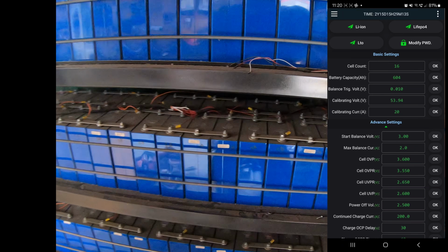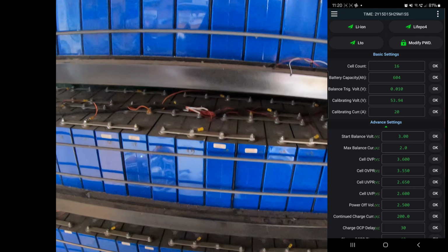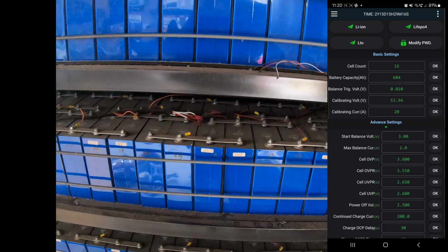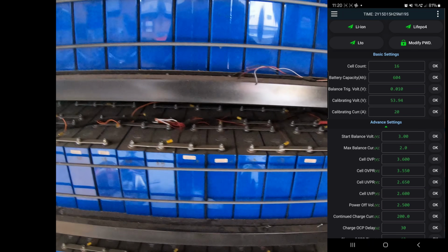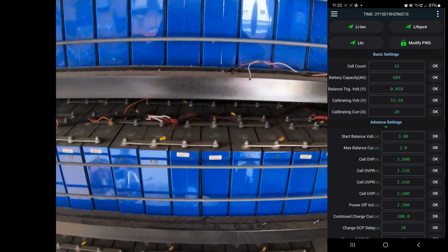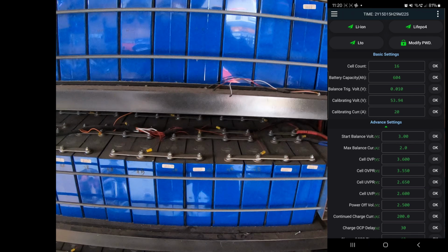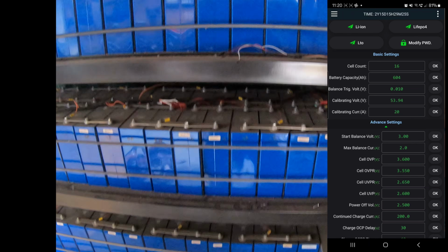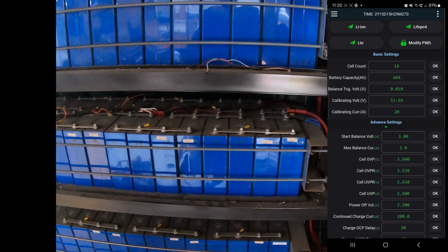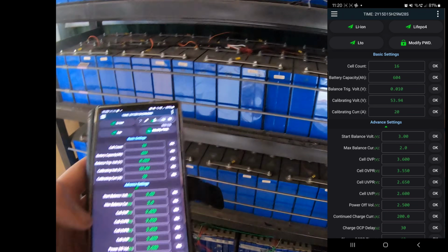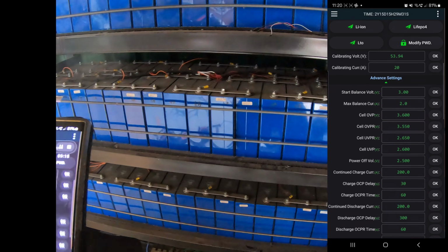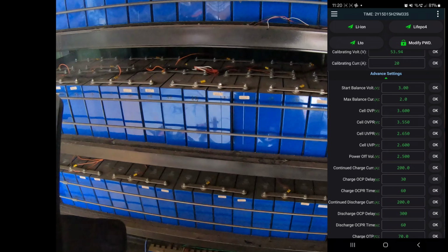What we do is periodically ramp the voltage up to 57 volts so that we can give the balancer the best chance possible. We do that for about a month, and then we'll turn the voltage back down again. We do that once a year, and it's been happy like that. We never see a huge cell difference, right? The max balance charge is maxed out to 2 amps, of course it is.